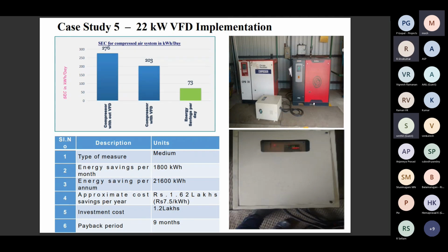Next, this is another example, a common VFD for two compressors, so only one compressor is running at a time. So they are able to save another 73 units per day, nearly 21,600 units per annum. The payback period is also very, very short, only 9 months.